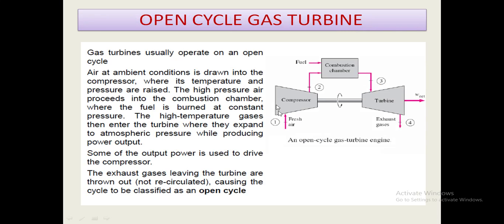Open cycle gas turbine: gas turbines usually operate on an open cycle. Air at ambient conditions is drawn into the compressor where its temperature and pressure are raised. The high-pressure air proceeds into the combustion chamber where the fuel is burned at constant pressure. The high-temperature gases then enter the turbine where they expand to atmospheric pressure while producing power output. Some of the power is used to drive the compressor. The exhaust gases leaving the turbine are thrown out and not recirculated, which is why the cycle is classified as an open cycle gas turbine engine.